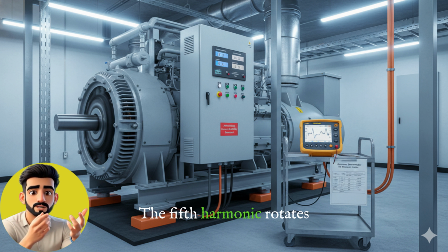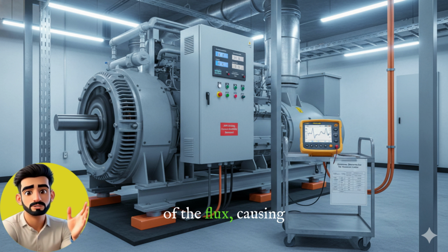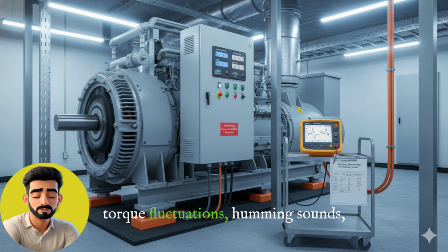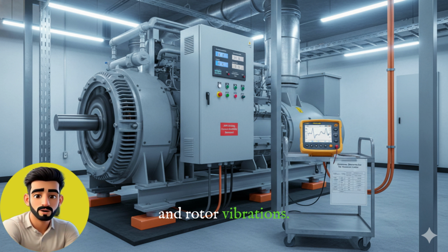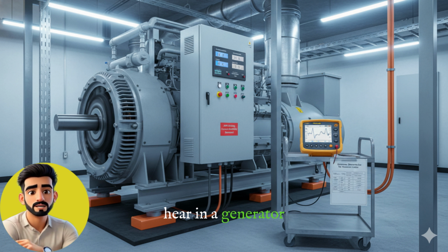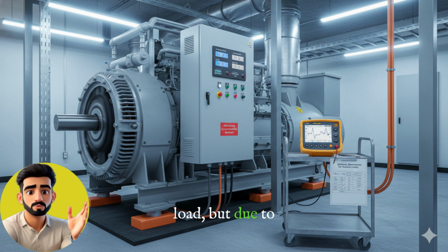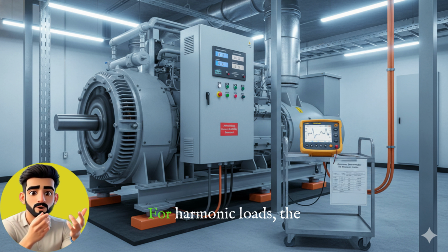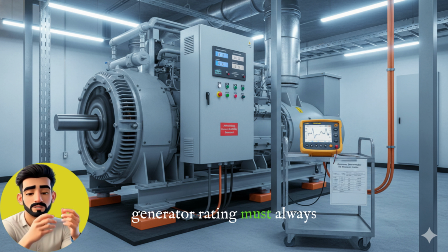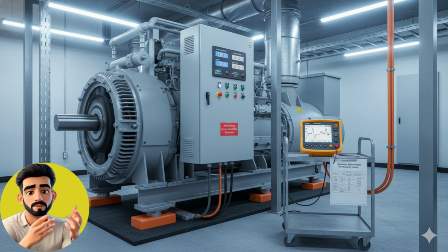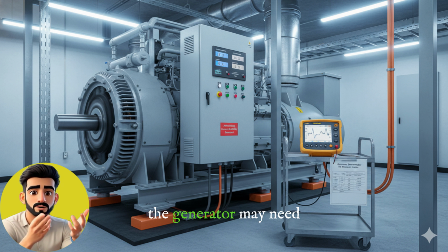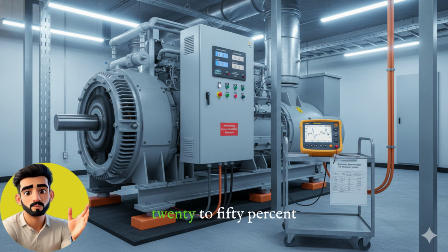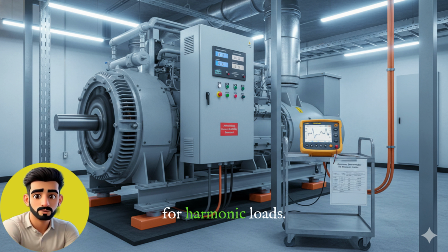The fifth harmonic rotates in the opposite direction of the flux, causing torque fluctuations, humming sounds, and rotor vibrations. Often, the humming you hear in a generator is not due to load, but due to the fifth harmonic. For harmonic loads, the generator rating must always be derated. According to many guidelines, the generator may need to be derated by 20 to 50% for harmonic loads. If derating is ignored, instability is guaranteed.